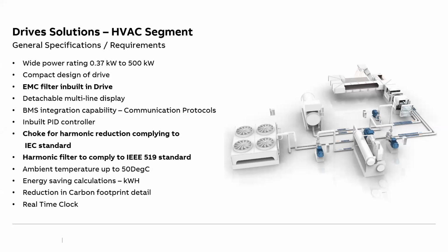Somewhere it could be 400 volt, 415 volt, 440 volt, 460 volt. So whatever the supply voltage, the selected VFD should be suitable for that supply voltage. It shouldn't happen that if you are changing the location, or dispatching to some other location, and 400 volt or 415 volt is not available, there only 440 or 460 is available, then the same VFD should be able to work properly in all the locations. Then the kilowatt rating, that's a very basic selection.